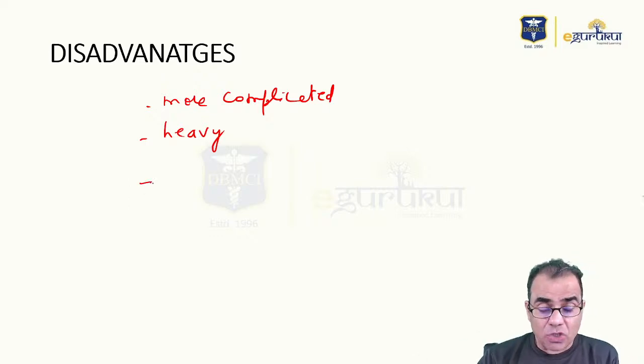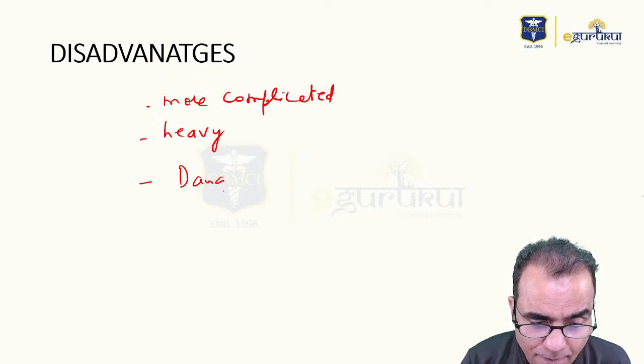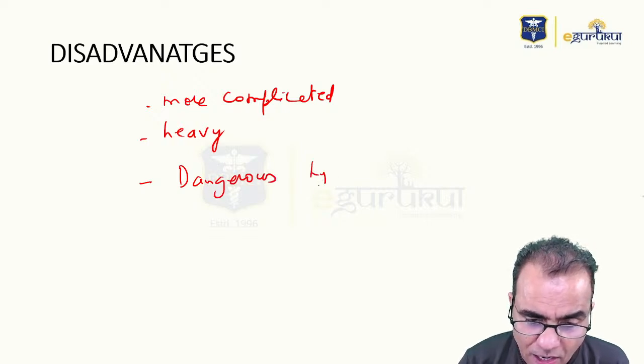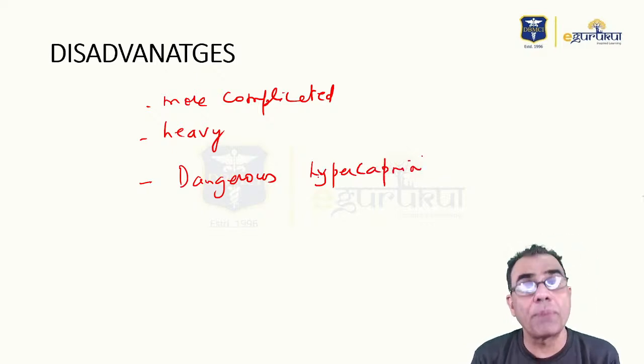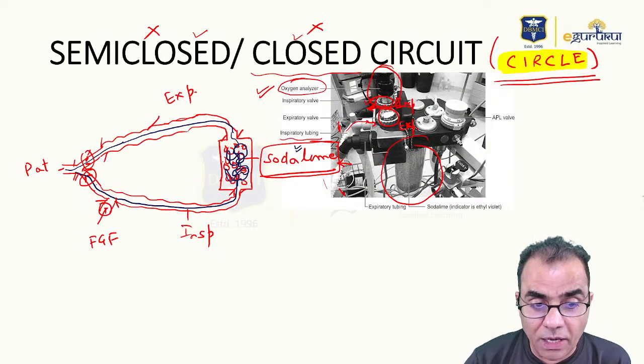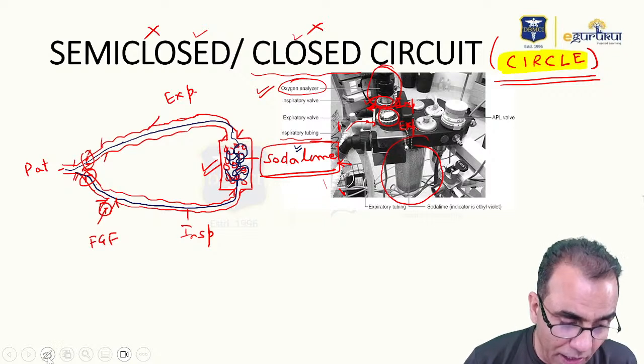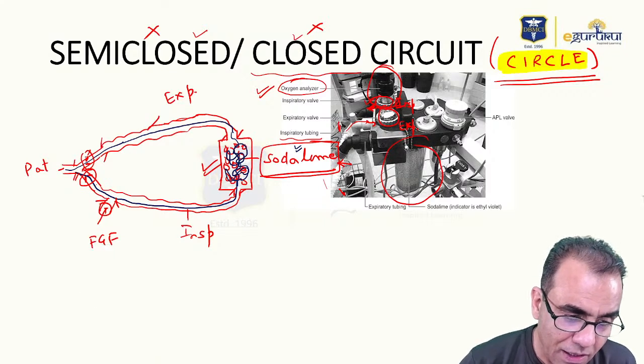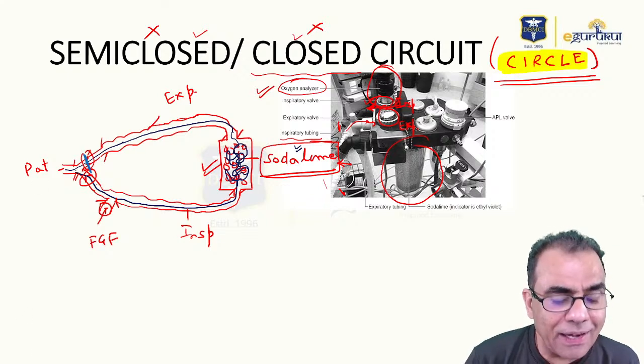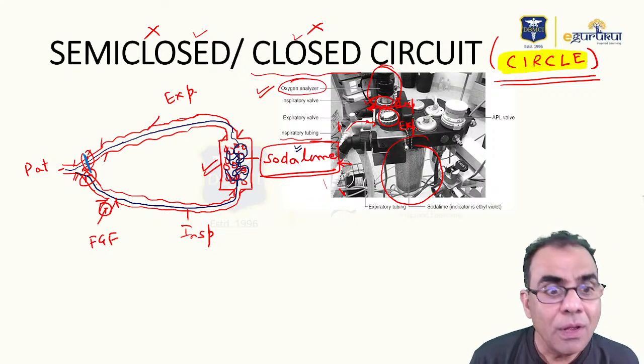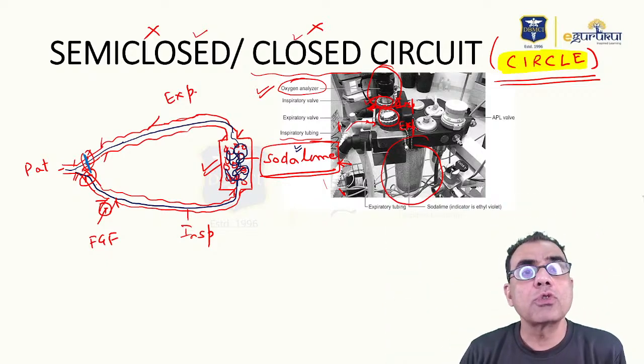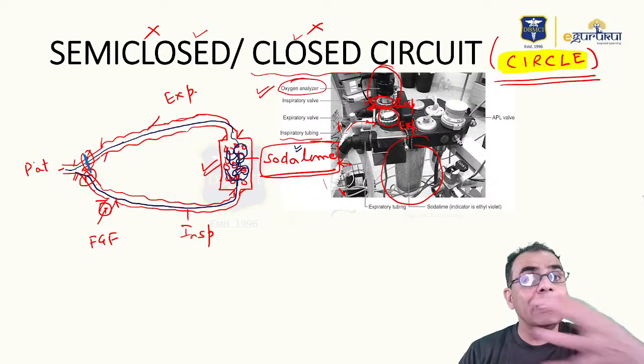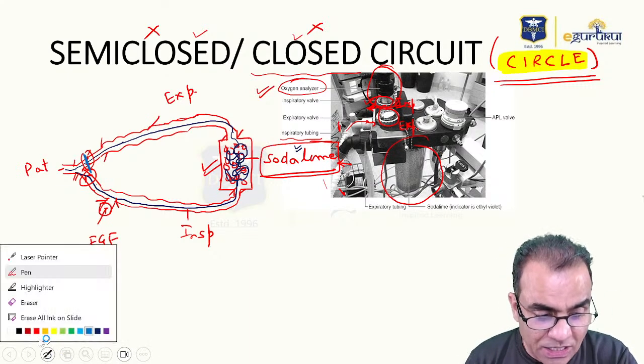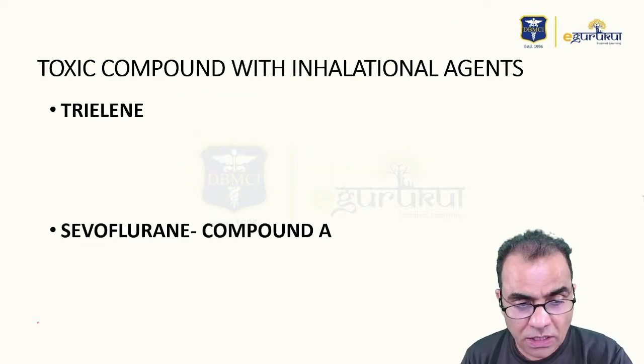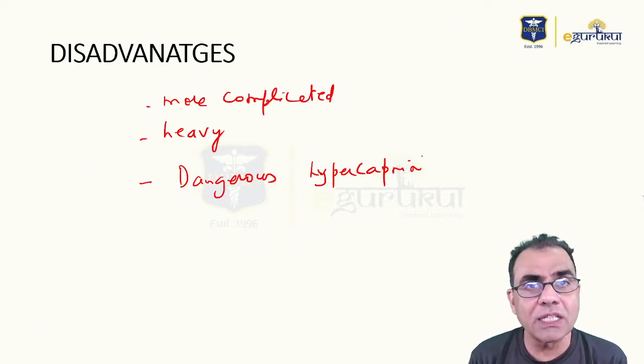Then secondly, there is risk of dangerous hypercapnia. Why? If soda lime becomes exhausted, and more importantly, if this valve gets stuck, then expiratory gases will not reach the expiratory limb and they cannot be vented out into the atmosphere. So where will they go? They will accumulate in the patient and the patient may develop dangerous hypercapnia. So that is another disadvantage, that there is risk of dangerous hypercapnia.